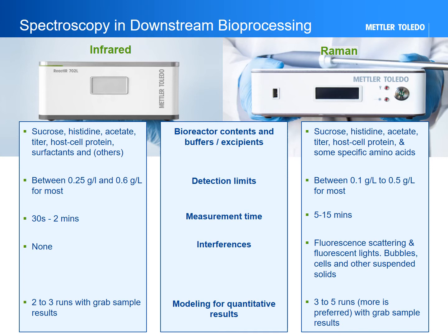While mid-infrared FTIR observes the fundamental and unique vibrations of each molecule and Raman observes the symmetrical bonds or dipole moments, both techniques often provide highly similar quality of information for all common molecules of interest in downstream bioprocessing. While detection limits are generally equivalent, speed of response tends to be faster for mid-infrared versus Raman, simply because Raman must collect more light over a longer period to achieve the same signal-to-noise levels. In chromatographic load or elution monitoring, the speed of mid-infrared FTIR can offer distinct advantages.